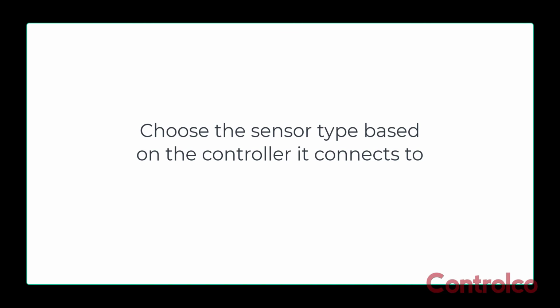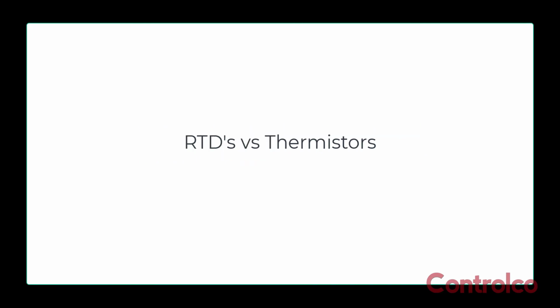So if we have a controller that accepts both types, which one do we pick? So let's say I have a 100 ohm platinum RTD. That means at whatever the reference temperature is, it will be 100 ohms. At 90 degrees, it might be 110 ohms. And I'm just going off the top of my head. I'm not looking at a chart here, so I could be completely off. But it's that small of a change.